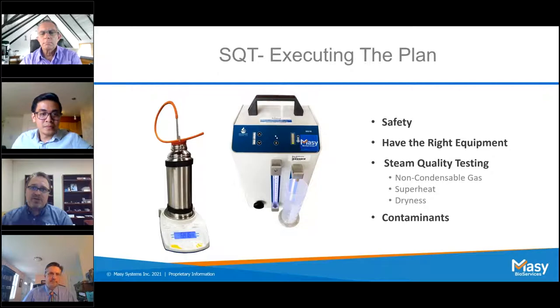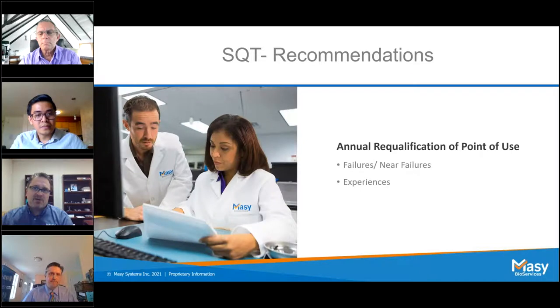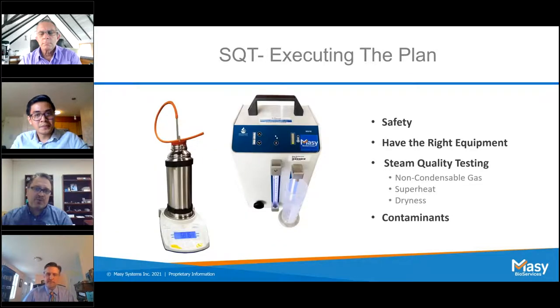Kind of talking about the how a little bit. Basically those devices are attached and they're used to run the three tests that we have. I think I covered that pretty well as we went through each. How many sets of tests do we do for each one of these? Each time we run a test, we do it three times. We need to have three successive passing results for the steam quality test to be successful for those three types of tests. So you could look at it as nine runs total. Each test is done three times in a row.